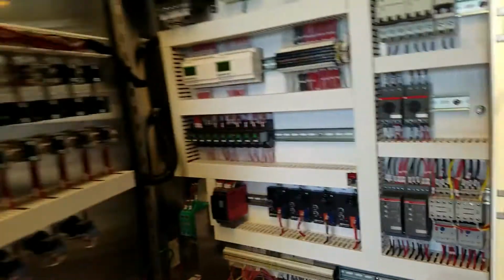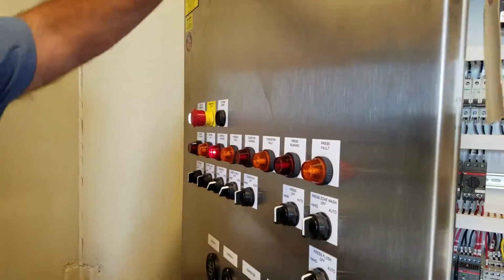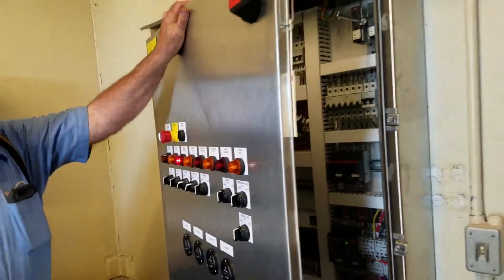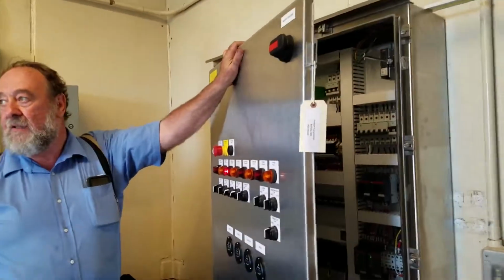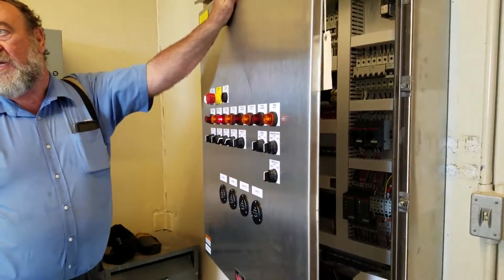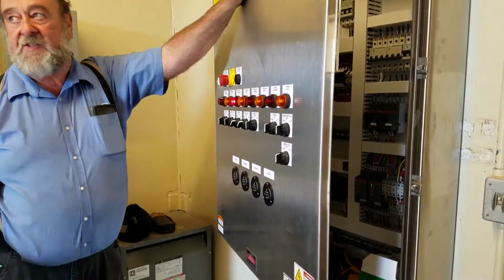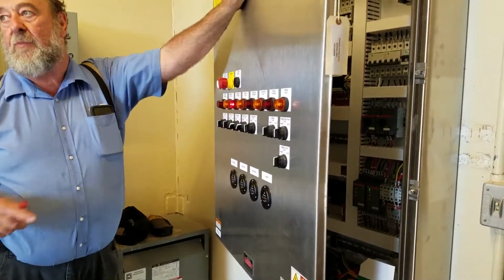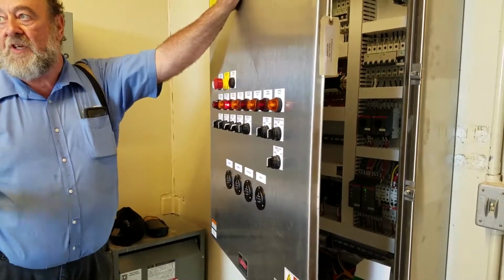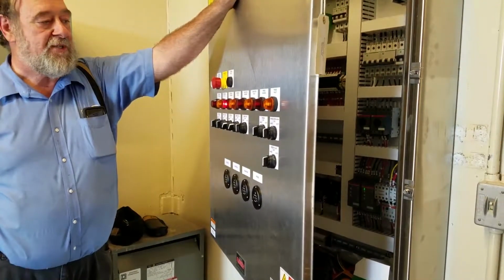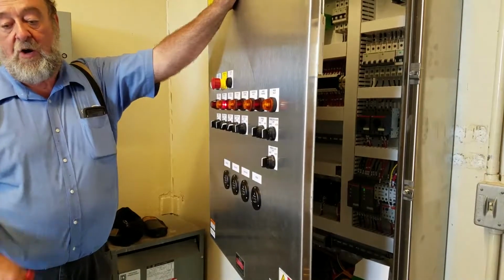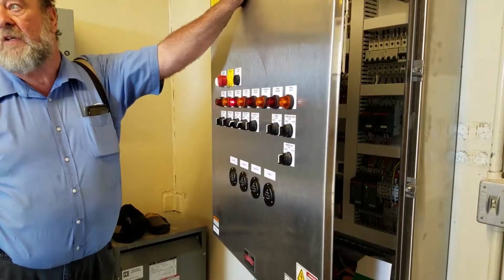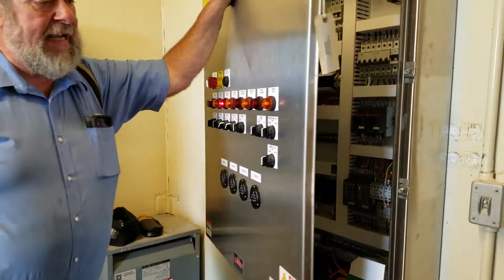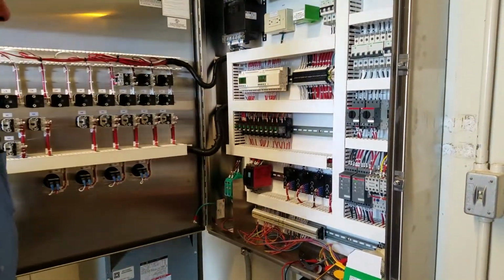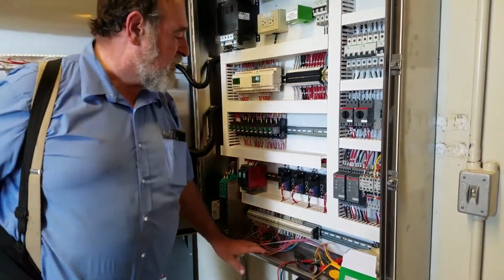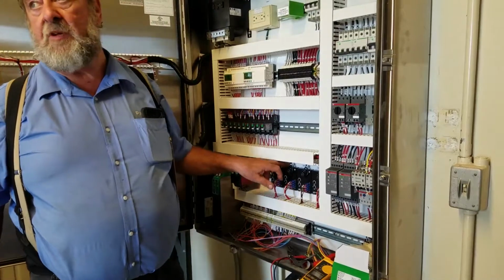Got it. Now, some plants have the policy that operators can push this reset button without a problem. That way, if you get a glitch, you got a loss of one phase coming into the plant, you just go around pushing reset buttons on the various equipment, things are up and running again, and boom, you're back in business. Some plants say if you got to open this panel up, you get an electrician involved. It's a good idea to have somebody with some mechanical expertise check things out if this has to be reset.